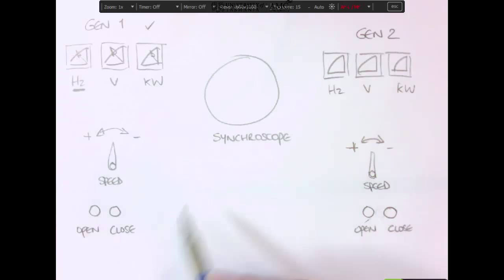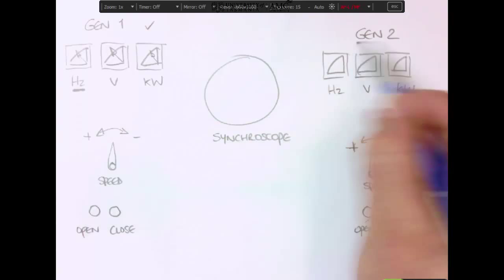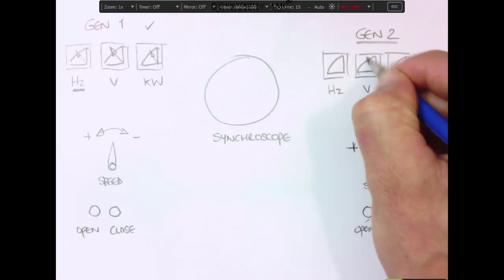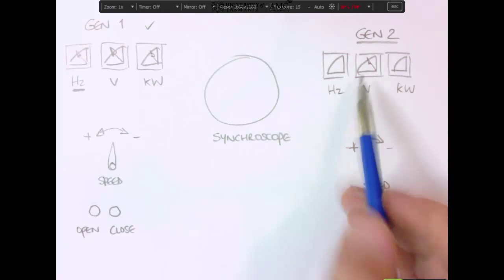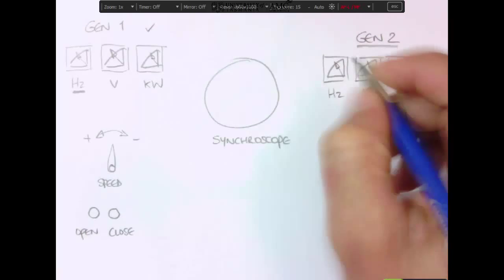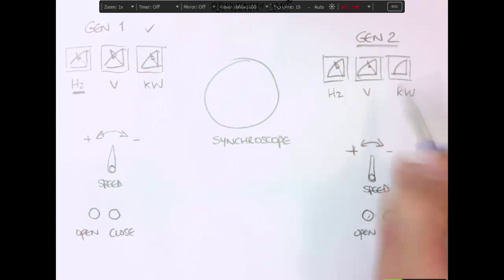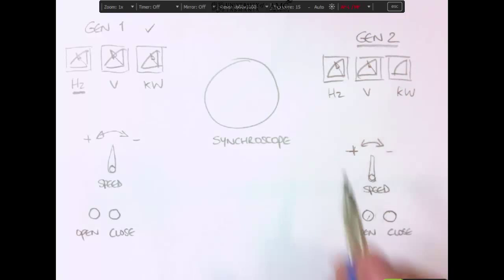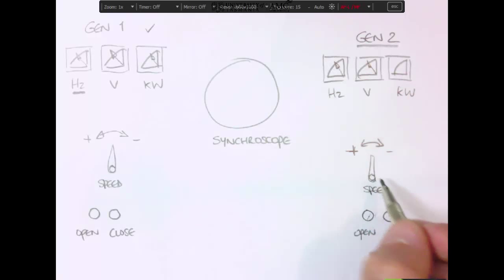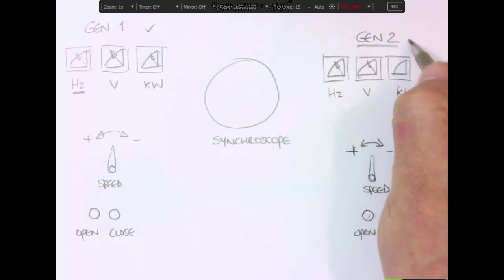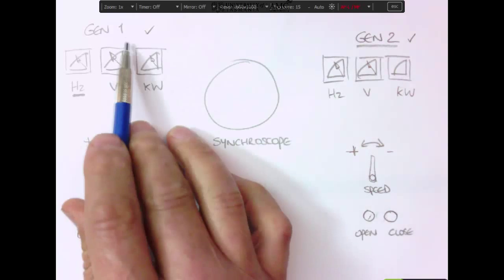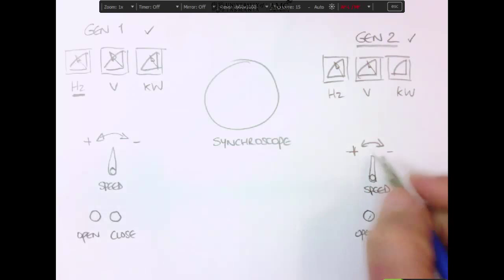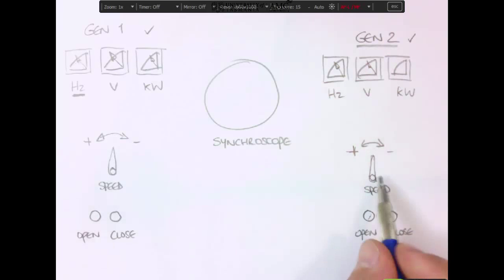Okay. Now, if I want to bring another generator online, then I start up my generator 2 and it starts producing 415 volts. It should be somewhere around 50 Hertz as well. It's going to have no kilowatts because it's not on the board yet. Now, I can also adjust the speed of generator 2. This becomes the incoming machine. This one's on board, this one's incoming. And if I play with the speed control on my incoming generator, then it's going to adjust the frequency.